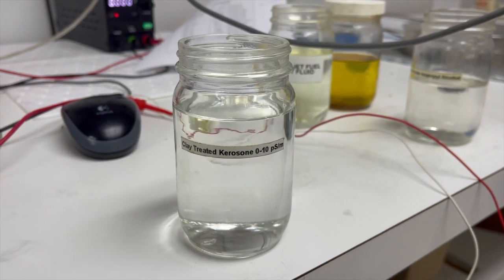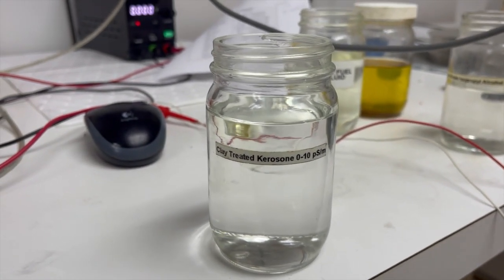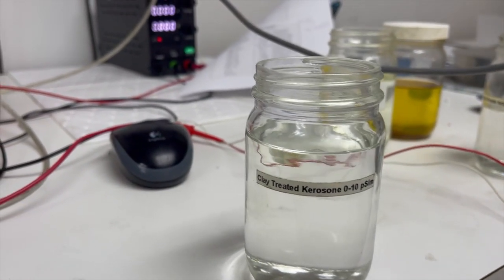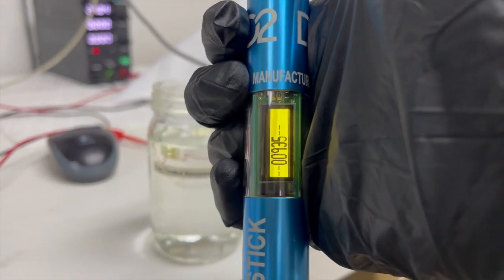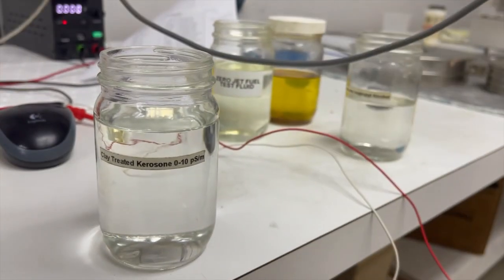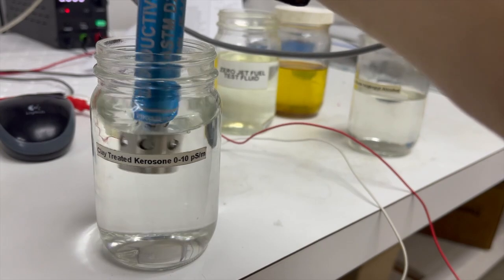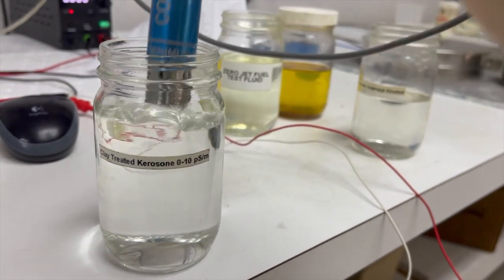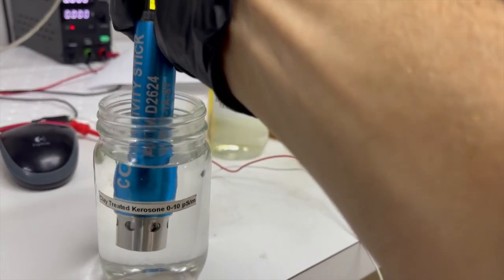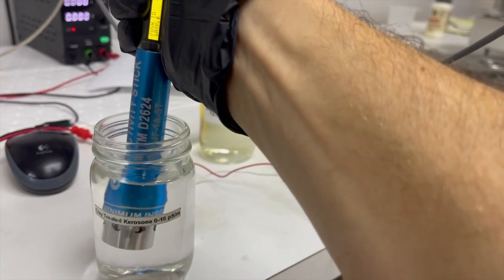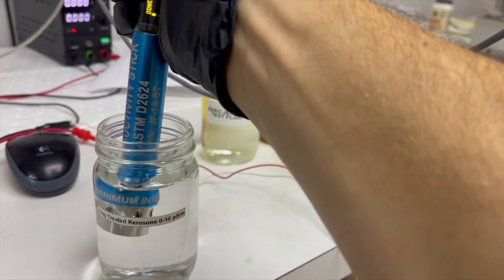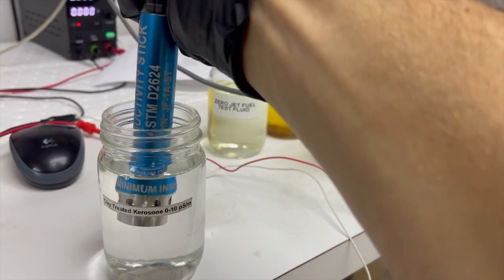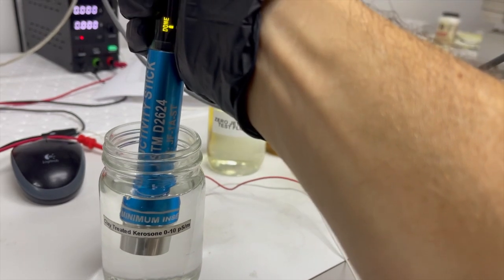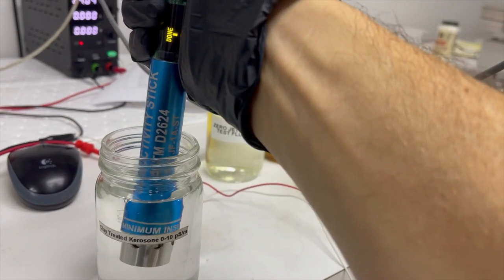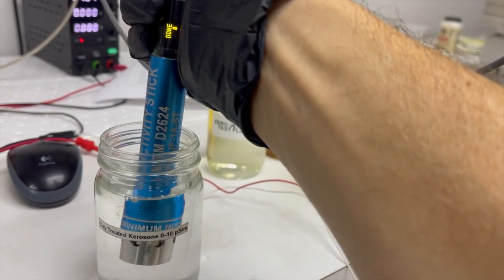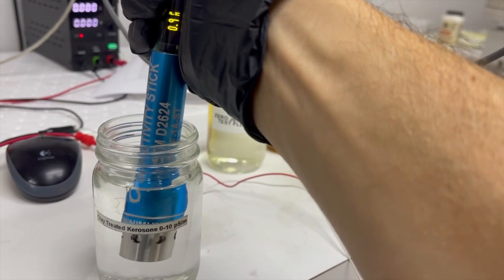So we have our 0 to 10 picosiemen per meter fuel sample here, and we're going to get a reference measurement of that. So we'll dip the sensor tip in, stir it about a minute, and then push the sample. Wait for it to go all the way through the cycle. Try to stay as still as possible.